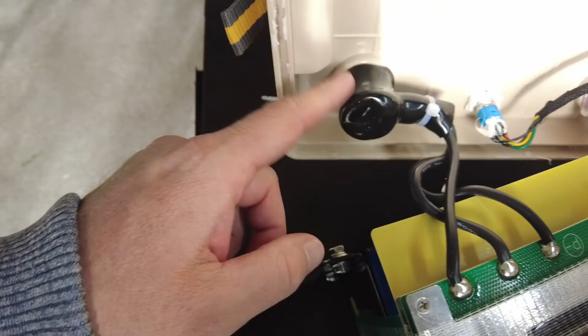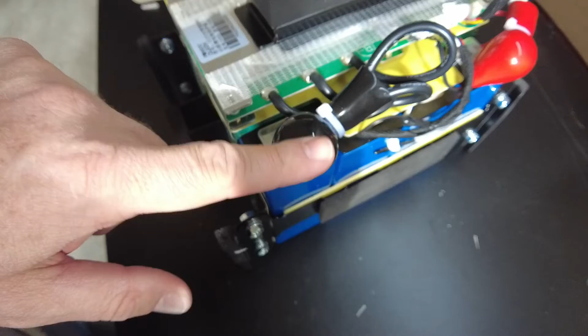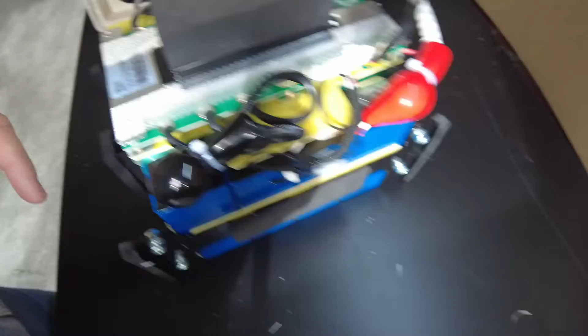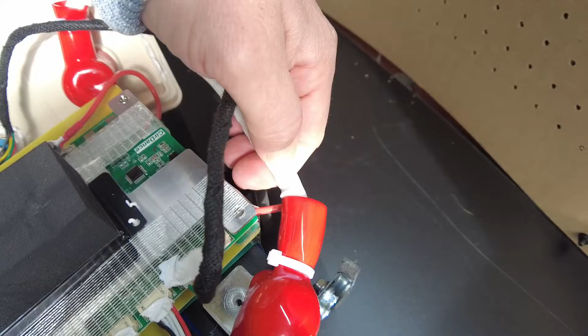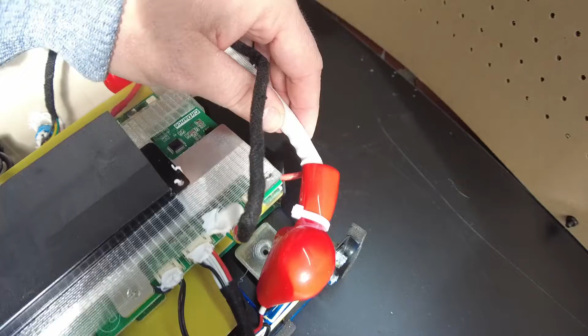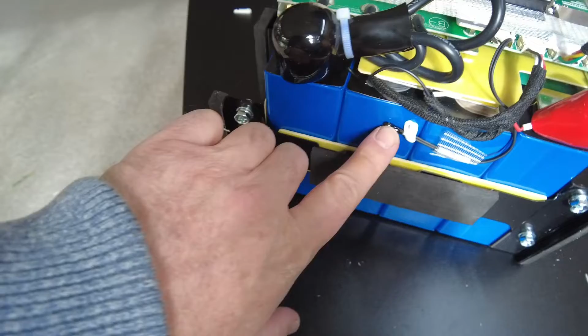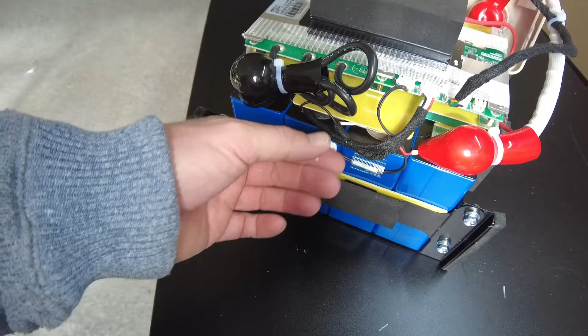Everything is covered that could possibly short - that's handy, I haven't seen that in other batteries. The terminals are covered here and at the top. This feels like one solid cable - I don't know the exact size, but it feels quite large, and it's also covered with a rubberized or siliconized heat shield. There's the battery temperature sensor, so we need to test if the low temperature disconnect actually functions. The balance leads are here and very well protected too - that's something you don't see a lot, but it's handy since those can short out as well.